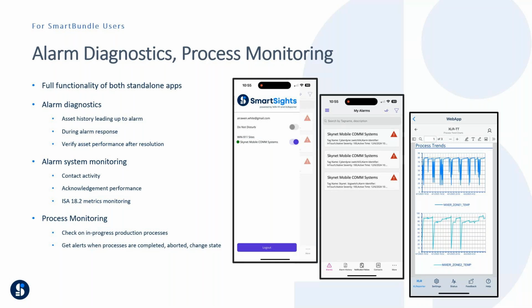You can monitor the health of the asset during the alarm response and verify that it's returned to normal, say, after the resolution. It allows you to actually monitor the alarm system itself. You can monitor the contact activity, what's happening as alarms are being relayed to your Win911 users. Are they acknowledging those alarms? Are there communication issues reaching them? How is their acknowledgement performance over time? You can also use this to track ISA 18.2 metrics like chattering and stale alarms, bad actors.